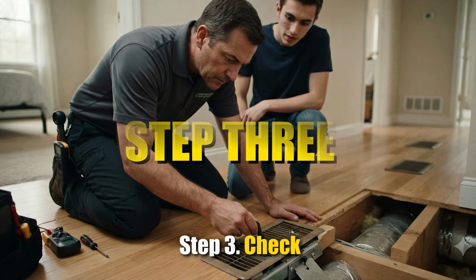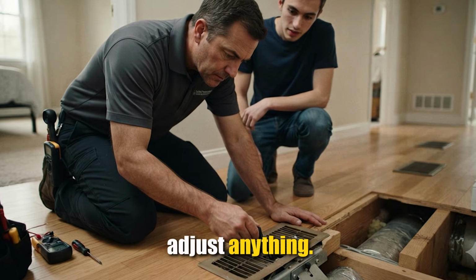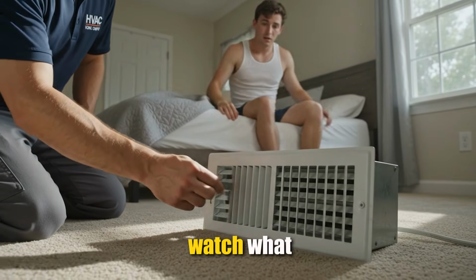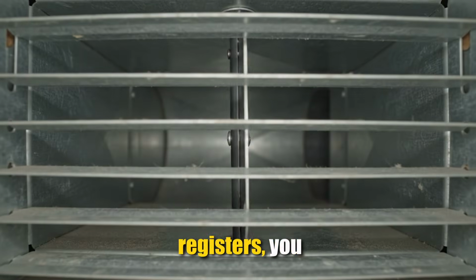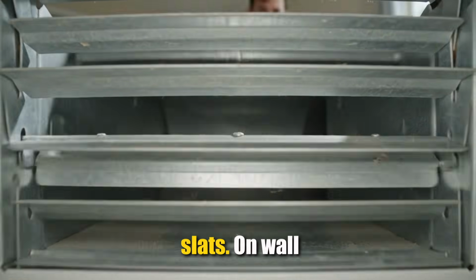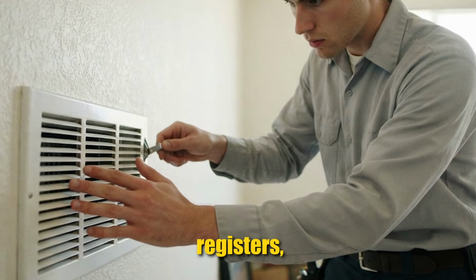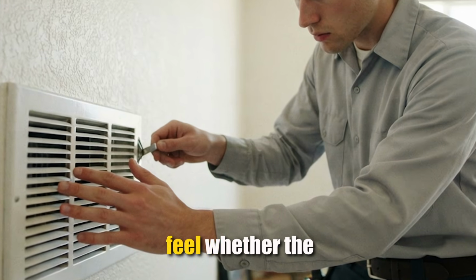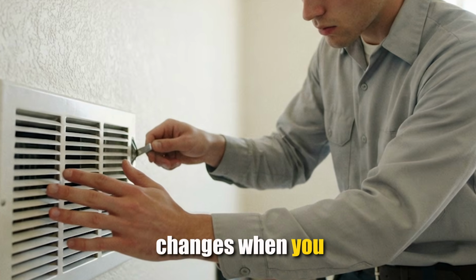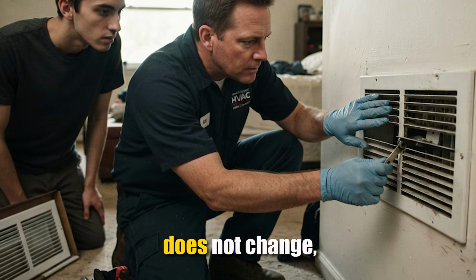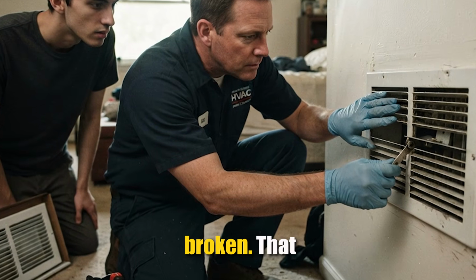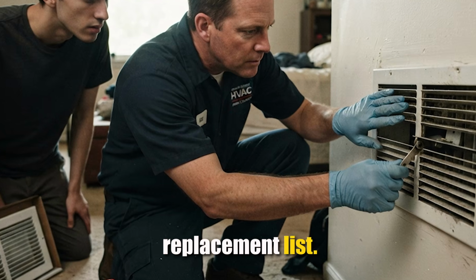Step 3. Check every register damper before you adjust anything. Move the lever on each one and watch what happens. On floor registers, you can sometimes see the blade moving through the slats. On wall and ceiling registers, hold your hand near the vent and feel whether the airflow actually changes when you move the lever. If the airflow does not change, the damper mechanism is broken. That register goes on your replacement list.